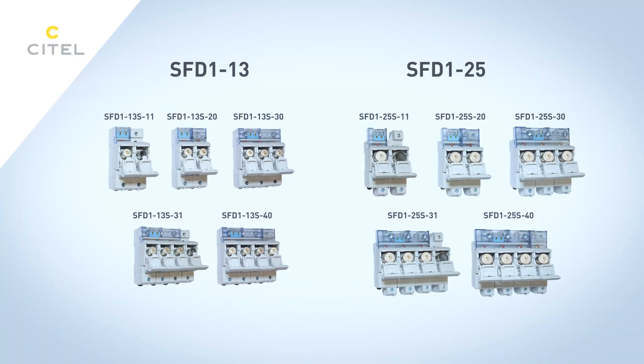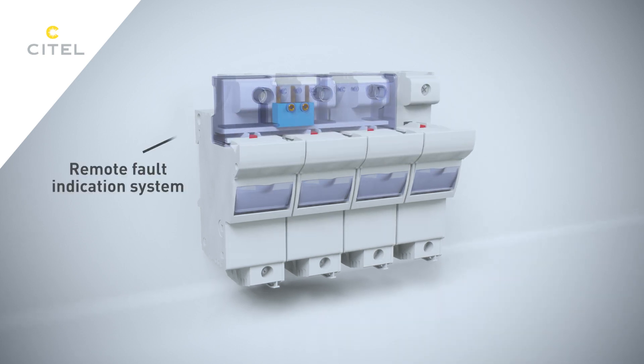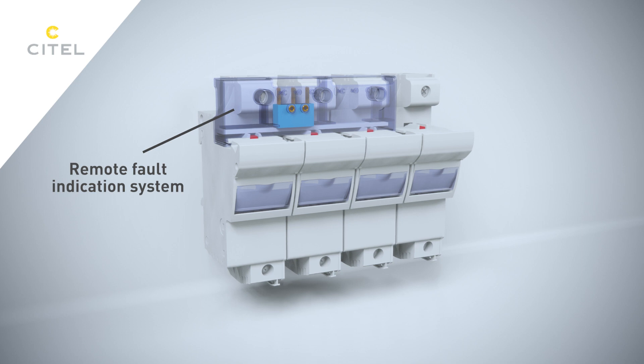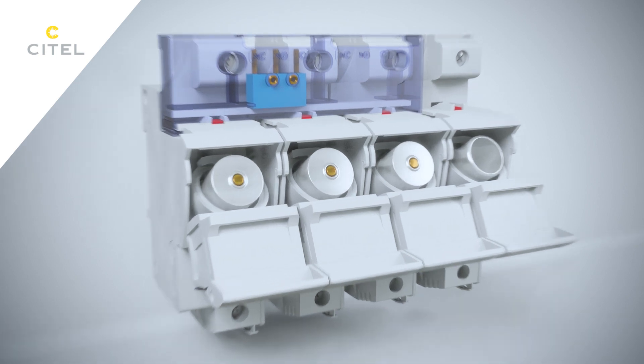SFD1-25 and SFD1-13 fuses are available for all types of network: IT, TT, or TN. The range is available in single-phase, three-phase, and three-phase plus neutral, and the fuse holder is equipped with a remote fault indication system. The fuse status is signaled by a striker.